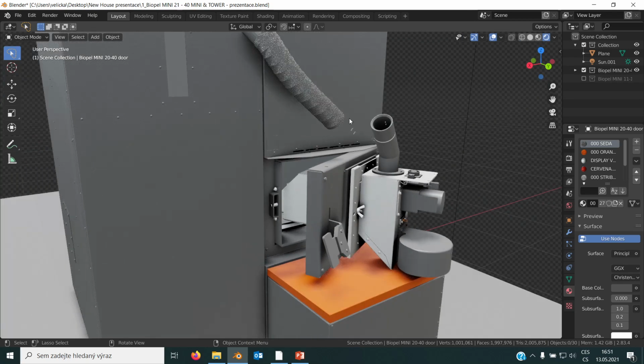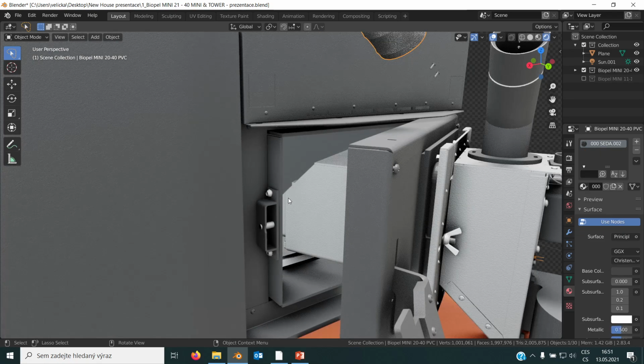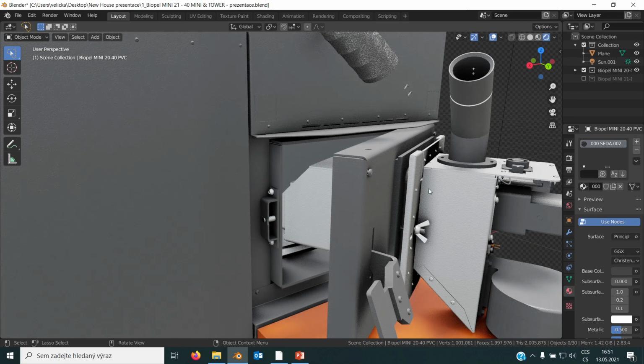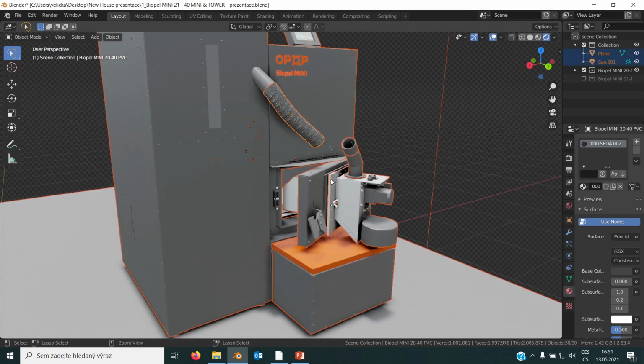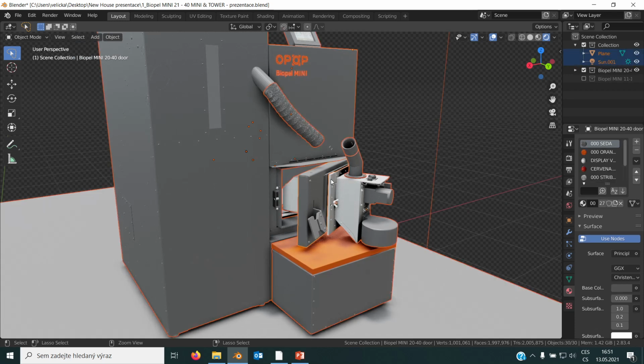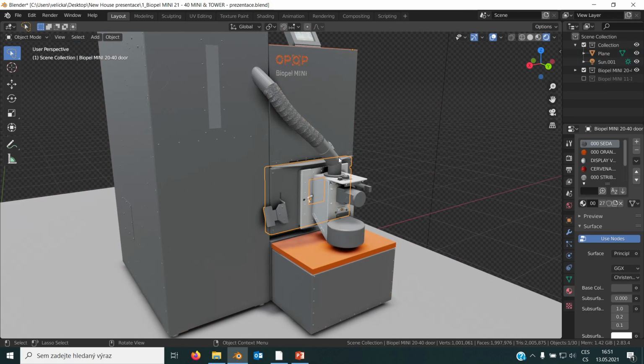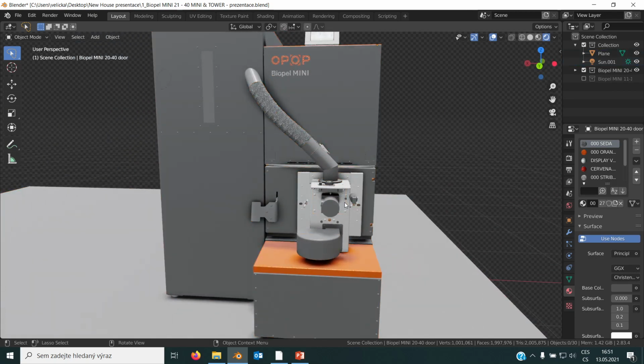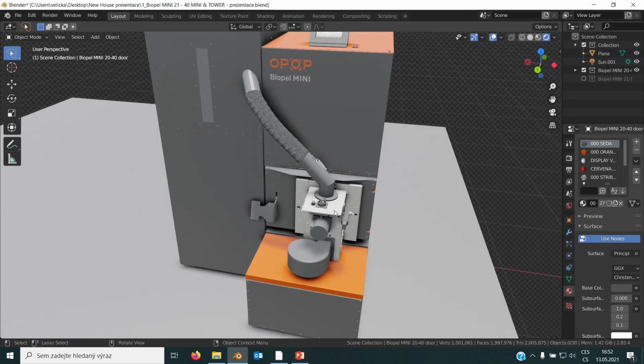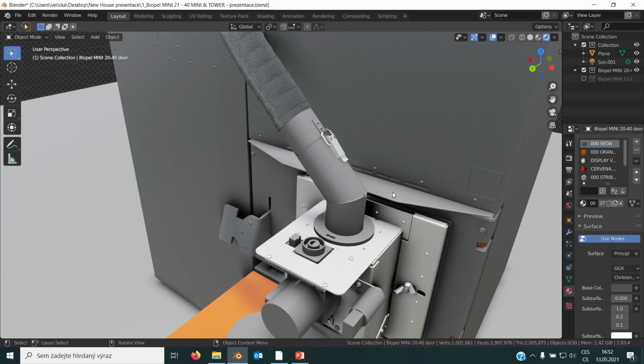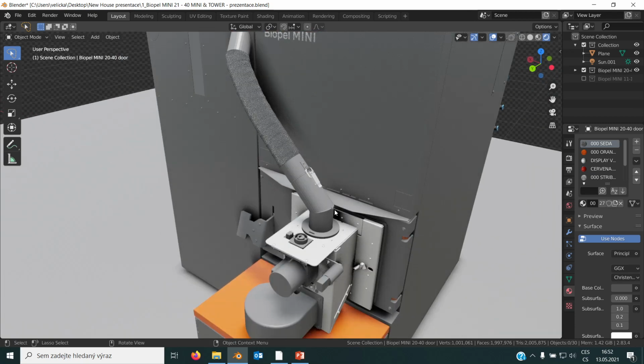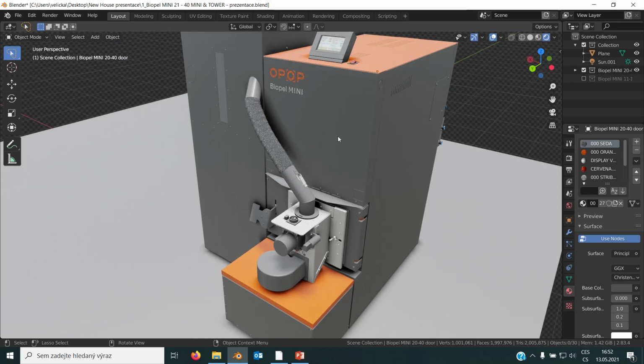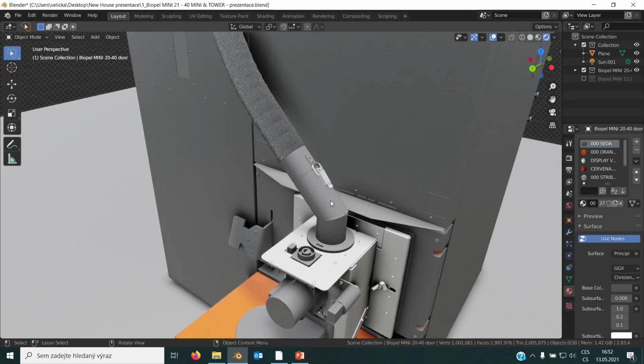To open the door fully, you have to first disconnect the PVC hose, then move the protection plate up, and then you can open the door, check the burner, clean the burner, and then close it again. So there are safety features regarding the opening of the door during operation to make sure that nobody will open the door during combustion. There is a small cover plate on the top here against heat, so that no heat goes below the cover, possibly damaging the control unit. So that's why there is a small protection here.